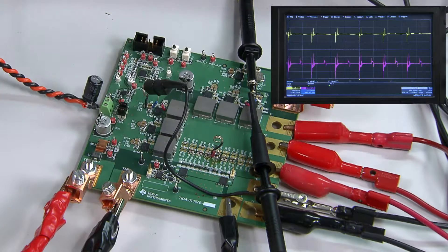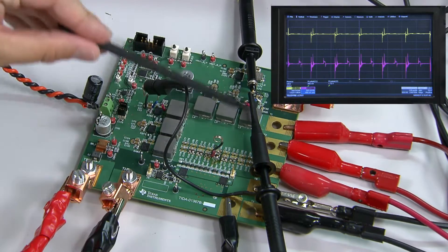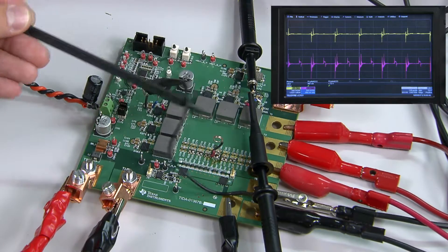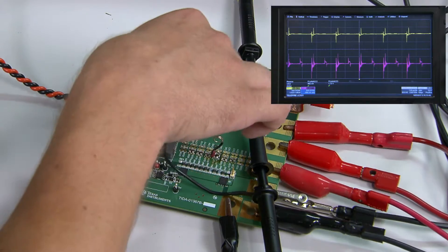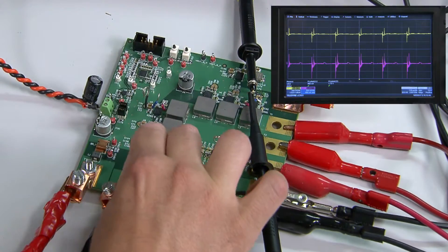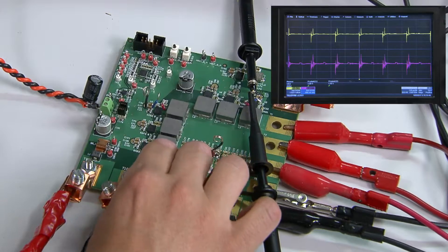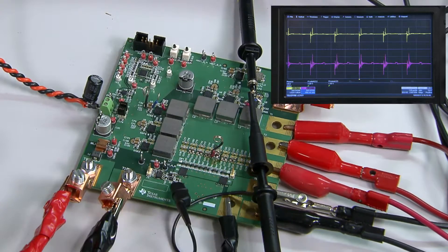On channel one I took my measurement with the probe ground placed locally at the phase, and on the second channel I've got this long ground lead which adds more ripple than what's really there. I can even get different measurements by moving the ground point from one of my ground lugs to another point on the PCB.